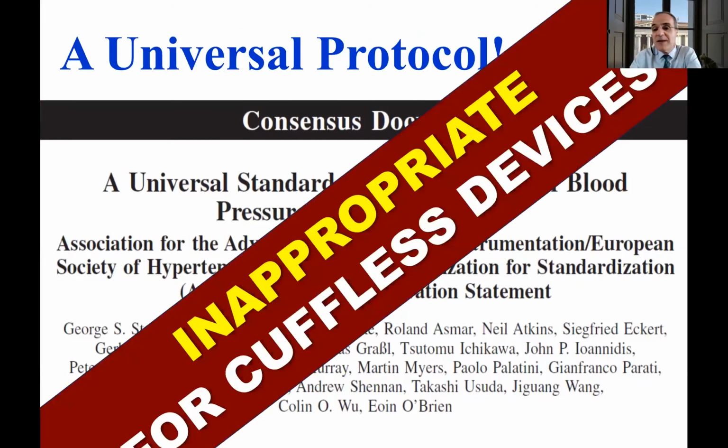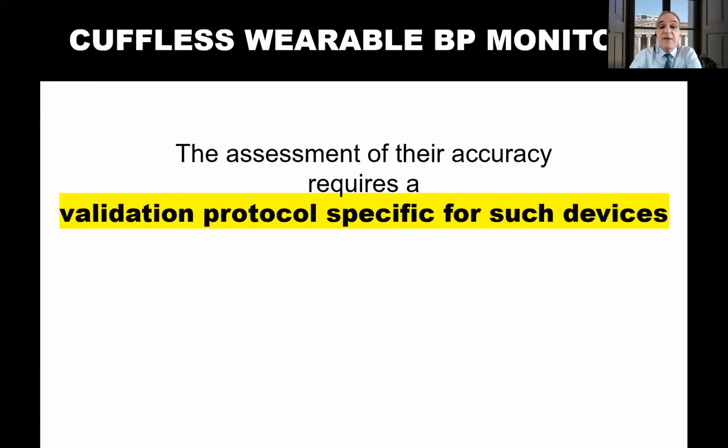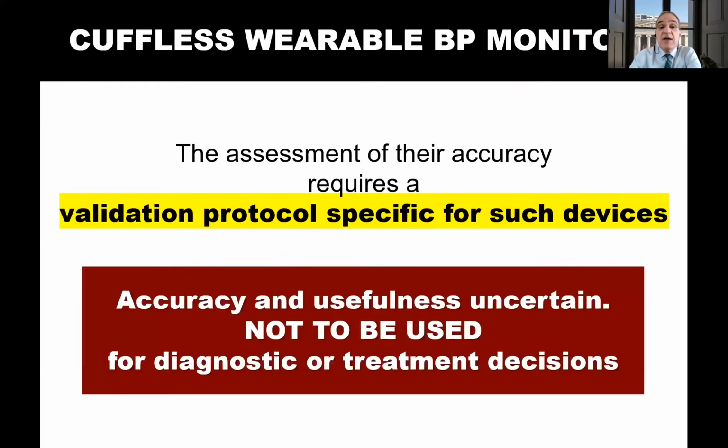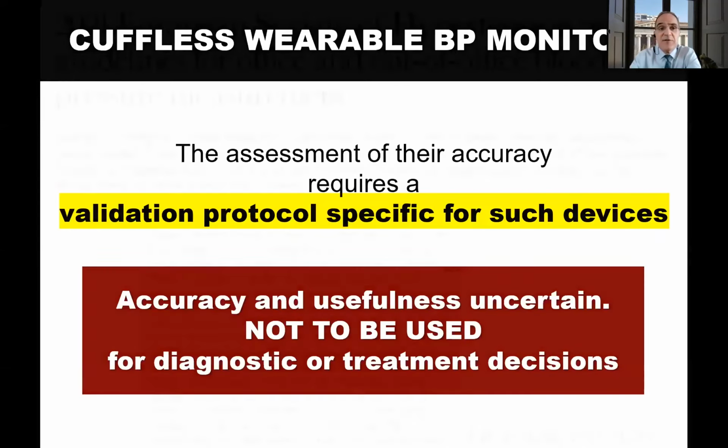We are now working with the ISO for 2 years or so to come out with a special validation protocol specific for cuffless devices. So we need a special protocol, and the official statement is that the accuracy and usefulness of cuffless devices is uncertain, and these devices should not be used at the present time for diagnostic or treatment decisions.